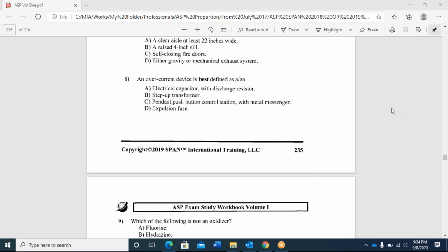So once a sudden increase in ampere occurs, it will damage, maybe it will create fire, maybe it will burn your appliances. So on the back side we have one small type of fuse, expulsion fuse. Let's suppose if your current increased to 90 ampere, and the capacity of this fuse is 90 ampere, the set limit.